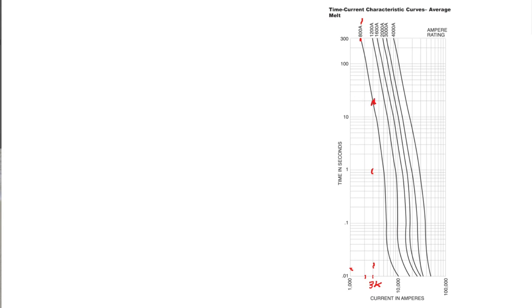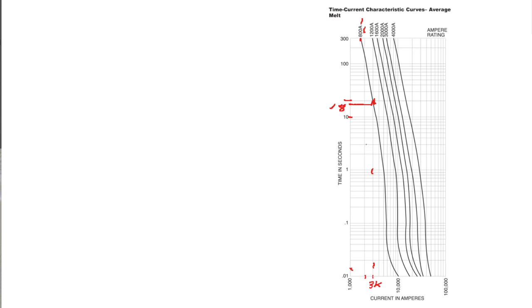We follow this over and we see that if this is 10 seconds, this is 20 seconds, so we're around 18 seconds. So an 800 amp fuse at 3,000 amps fault current will trip after approximately 18 seconds.